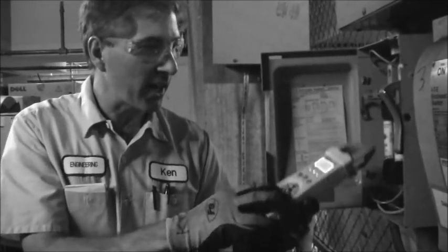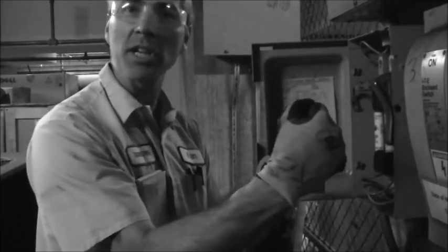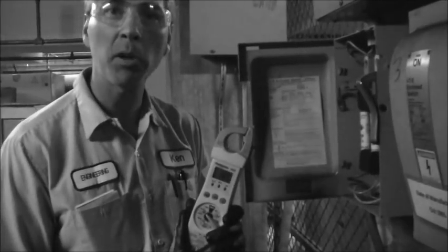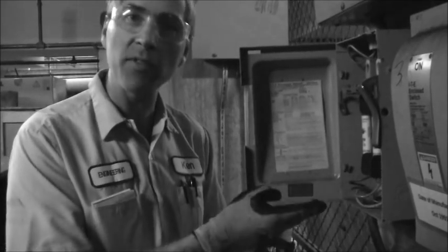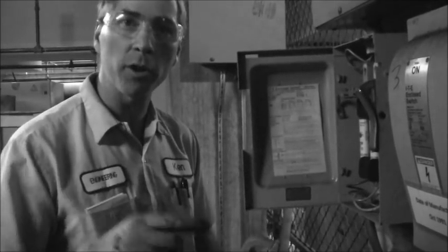So what I did was, with my unit off and verifying that I had no electricity, I took phase B, which is this one, and phase C, which is this one here, and I switched it. Then I put the meter back on, and I threw the disconnect on. And the compressor actually started. When it did that, it sounded like hell. It was a terrible compressor, and I was pulling 4 amps, way low amps. But it was also spinning backwards. On a 3-phase motor, when you change any of the 2 phases, you rotate that motor backwards.